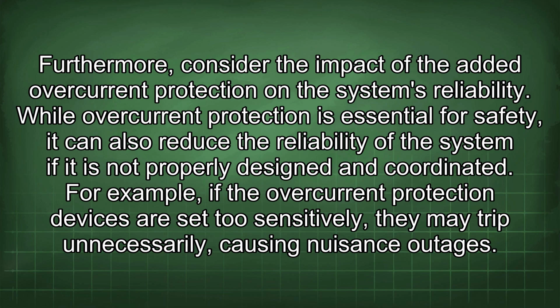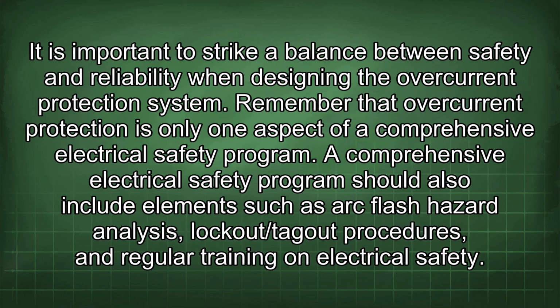While overcurrent protection is essential for safety, it can also reduce the reliability of the system if it is not properly designed and coordinated. For example, if the overcurrent protection devices are set too sensitively, they may trip unnecessarily, causing nuisance outages. It is important to strike a balance between safety and reliability when designing the overcurrent protection system. Remember that overcurrent protection is only one aspect of a comprehensive electrical safety program.